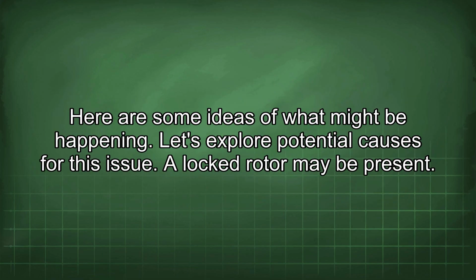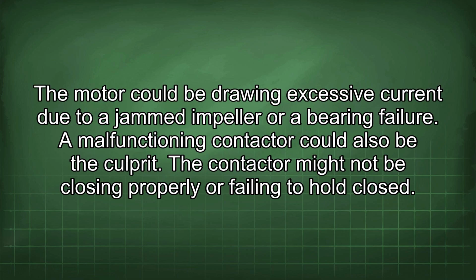Here are some ideas of what might be happening. Let's explore potential causes for this issue. A locked rotor may be present. The motor could be drawing excessive current due to a jammed impeller or a bearing failure.